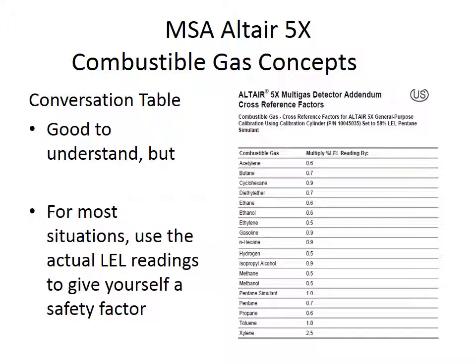So if you want to use this meter or the calibration table to understand where you're actually at, you would take the actual LEL reading on your meter and multiply by the percent LEL reading in the table. So we're looking at natural gas. If you're at 10% LEL of natural gas in a natural gas environment, ideally with that being methane, you would multiply that by 0.5, which is the conversion factor, and really where you're at is 5% LEL. Okay, so it's actually less than what's on the meter. But like I said, we don't want to get involved with pulling this conversion table out or remembering what it means in natural gas situations. Give yourself a safety factor. So if the meter's telling you 10% LEL, yeah, it might be 5%, but give yourself a safety factor of that 10%.